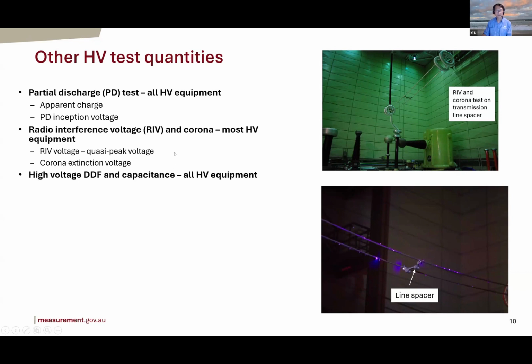And the other test is the dielectric dissipation factor, which is a measure of the loss or heat generated in the insulation. So you don't want too much heat generated. You don't want to have too much loss. And that's why this is also tested for most equipment.